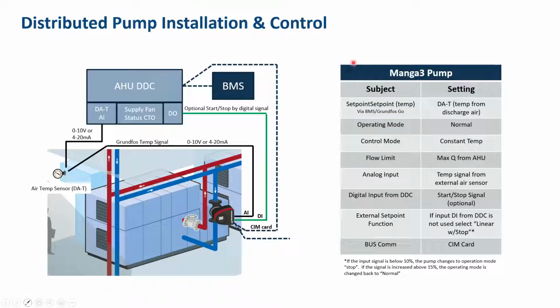What I have here on the right-hand side is a chart of a few of the points of data that are available when using a communications card with our intelligent pump. These are just a few of those points, and as we've gone out and installed our first systems here in the US, we've gotten a lot of great feedback from controls contractors on the amount of data that we have available when we're talking about a pump that is responsible for flowing that water, has integrated sensors and temperature sensors, pressure sensors, and an ability to estimate flow rate. It's a lot more that's available typically from a valve without adding any other hardware or without additional points on the BMS system.